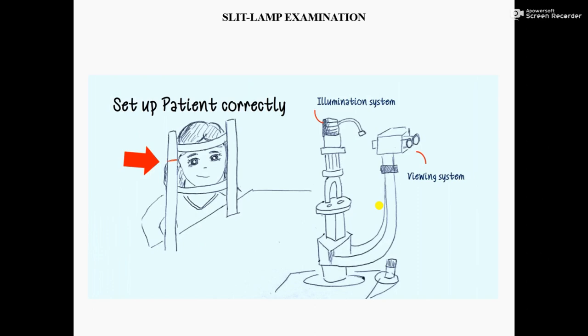Illumination system. A bright illumination system is one of the two fundamental requirements for a slit lamp. While halogen lamps are more expensive than tungsten systems, they provide a brighter, cleaner light and should be the system of preference. There should also be a means of controlling the intensity of the light.